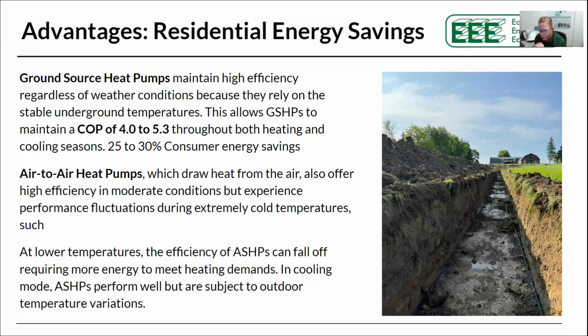The big thing to take away from this is that, unlike an air-to-air heat pump, as the outdoor temperature drops, we do not see an efficiency drop-off and we do not see a capacity drop-off, which is a big advantage to the ground source heat pump.